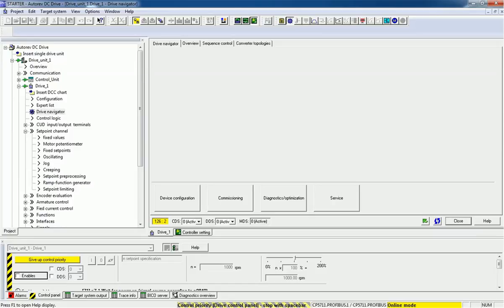In order to make maximum optimization from this motor, we need to calibrate some parameters and as per those parameters we will enter the data in commissioning. We are making tests for different parameters like field current, armature current, friction losses, and moment of inertia. We will do these tests from the optimization menu and get the data, then make the commissioning trial accordingly.